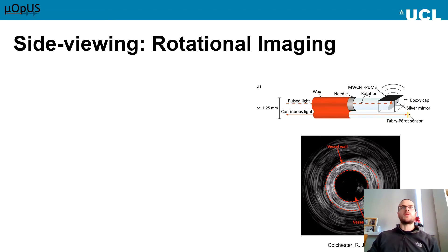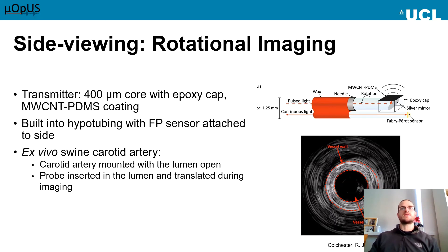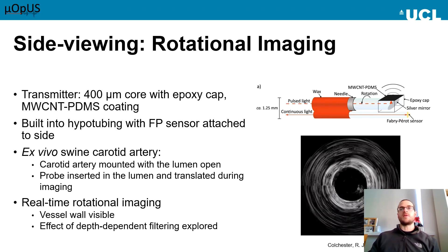Moving on from forward viewing, we have the other paradigm of side viewing. This is of interest for looking at vessel walls and luminal structures for many medical applications. Instead of looking ahead of the optical fibre, we transmit from the side surface. We polished the optical fibre surface to 45 degrees and coated it with a mirror so that the light from the fibre would be redirected to the side. We then built an epoxy cap onto this with an ultrasound generating surface and coupled it with an omnidirectional receiver. When we rotate the transmitter, we can receive an ultrasound signal in a rotational fashion to build up an image. This was tested ex vivo with swine carotid arteries, and we had a look at the effects of using depth-dependent filtering to optimize imaging.